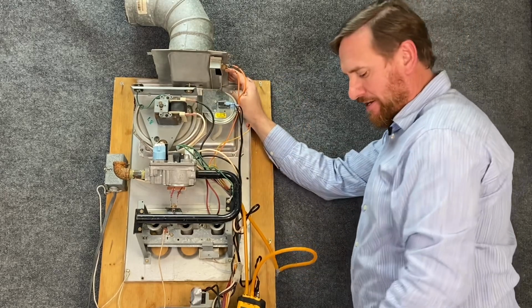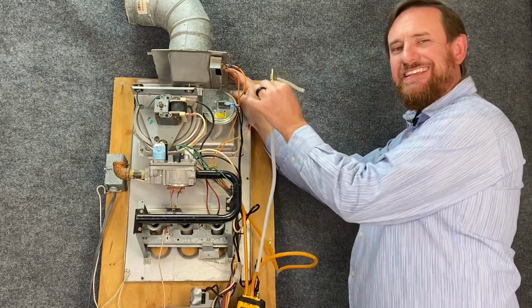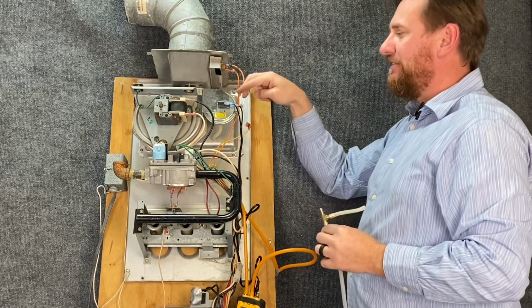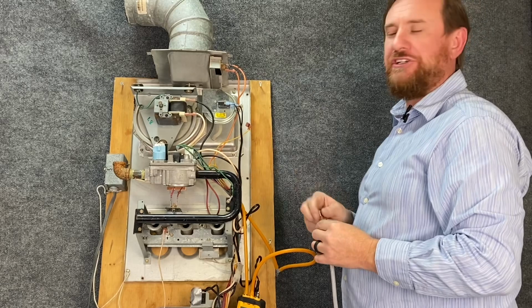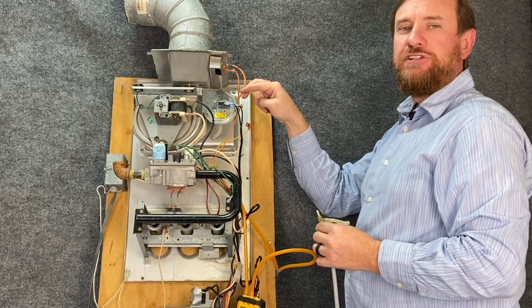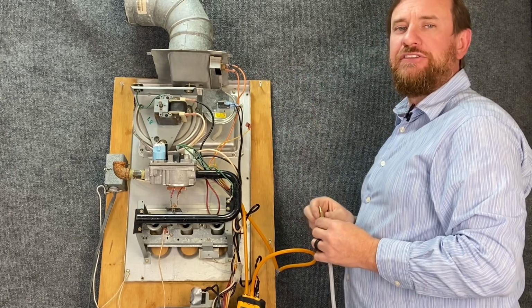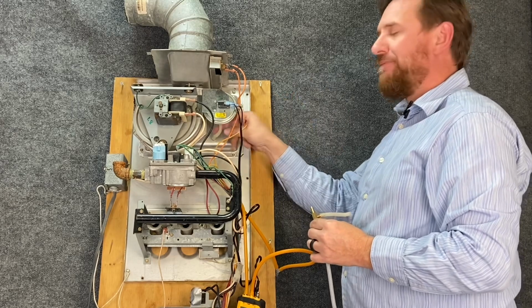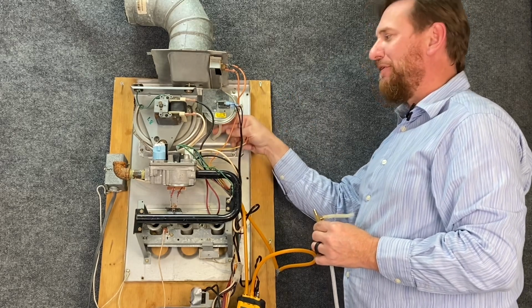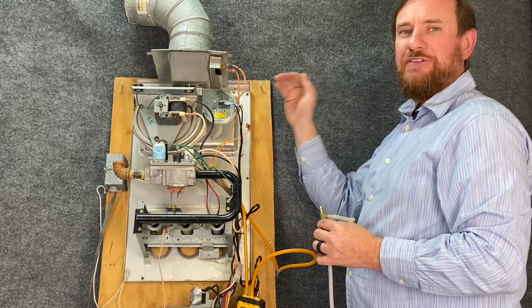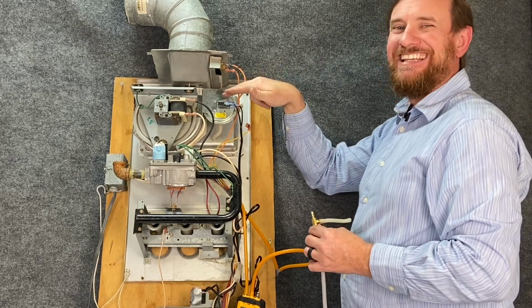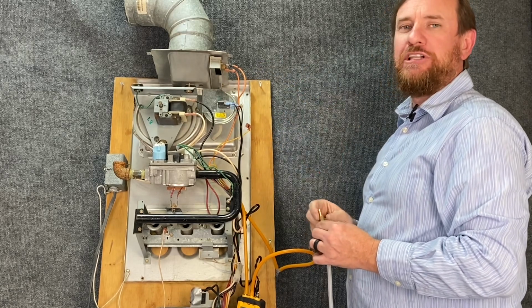To test it, the method I prefer is a T and a manometer, and check to see if the switch is open or closed with voltage. If I'm reading 24 volts, the switch is open. If I'm reading 0 volts, the switch is closed. Very simple. Don't suck on it. Don't pull too much pressure on it. You don't want to damage it. And if you have to replace it, go back to make sure it has the exact same inches of water column that it closes for.